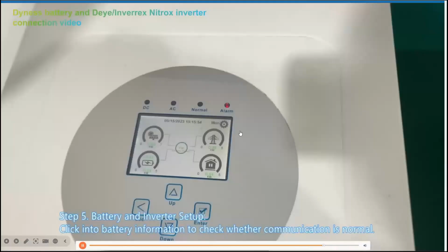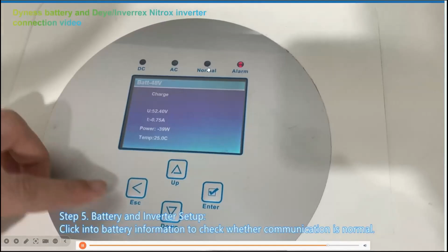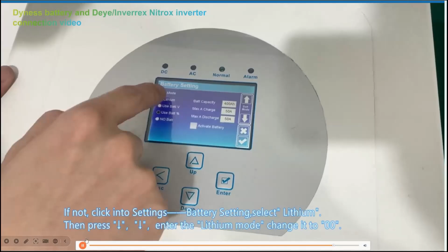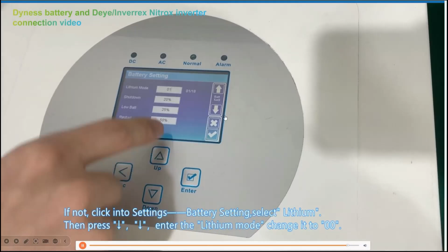After the connection is finished, we need to do some settings on the inverter to make the communication successful. First, we go to this page, battery settings, select Lithium battery, and then click down twice. To this page, which is for the battery type, and for Dyness battery it should be 00. You can press the screen and then change it. Yeah, and click OK. And then the communication should be normal.